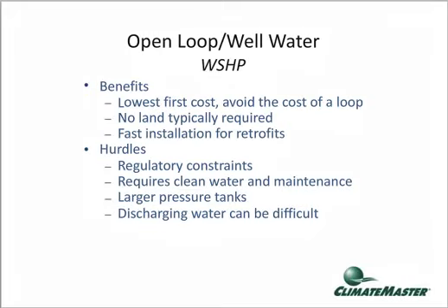Benefits. Well, it's the lowest first cost of any geothermal application that I'm aware of because, well, you avoid the cost of a loop. Typically, there's no large lands required. Fast installation for retrofits. I've done a number of them in one day. Some of the obstacles occasionally can be regulatory constraints. You always want to visit this first and foremost to make sure that this is something allowable in your area. It varies certainly from region to region, state to state.